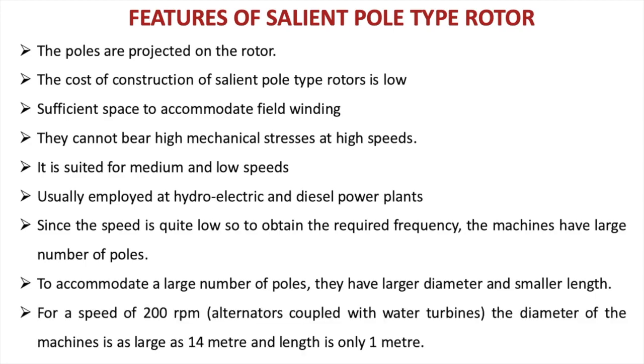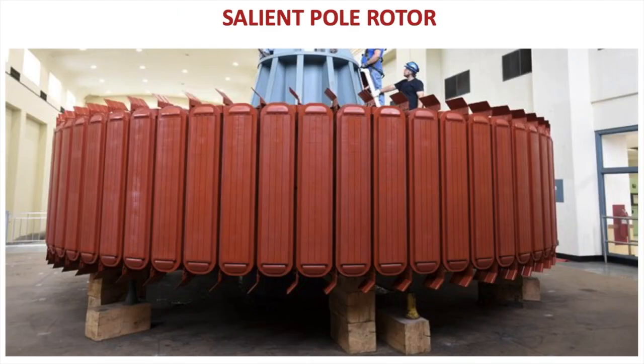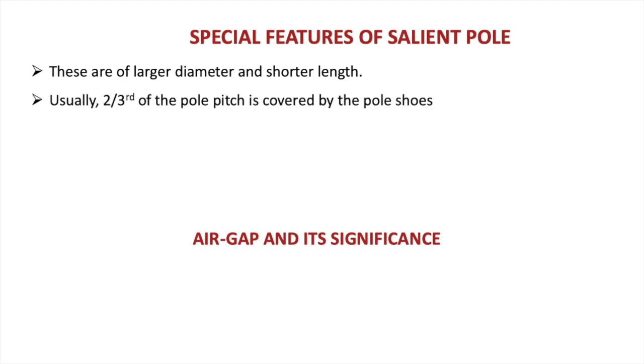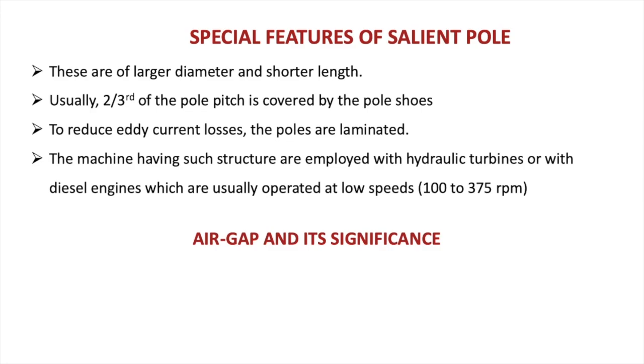For a speed of 200 rpm, for alternators coupled with water turbines, that is, in hydro generators, the diameter of the machine can be as large as 14 meters and the length is only 1 meter. You can visualize over here that the diameter is very large while the actual length is very small. And normally hydro generators are vertically mounted. Special features of the salient pole: these are of larger diameter and shorter length. Usually 2/3 of the pole pitch is covered by the pole shoes. To reduce eddy current losses, the poles are laminated. Machines having such a structure are employed with hydraulic turbines or with diesel engines, usually operated at low speeds from 100 to 375 rpm.